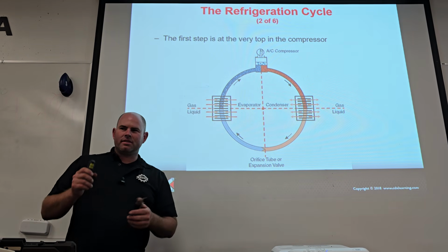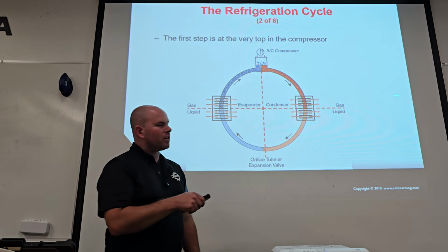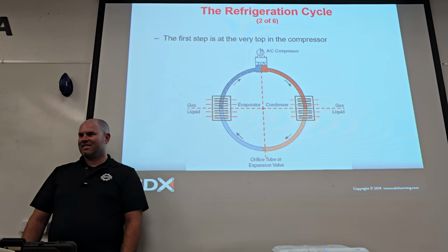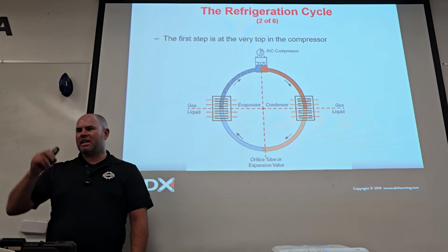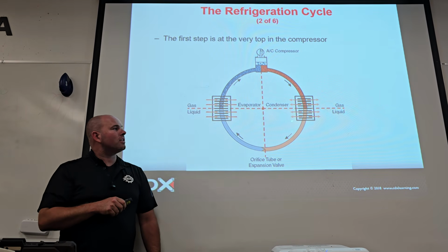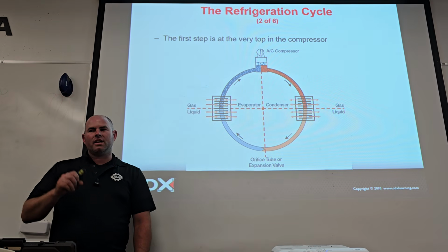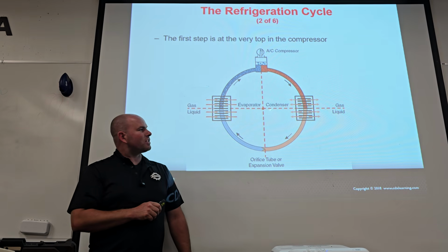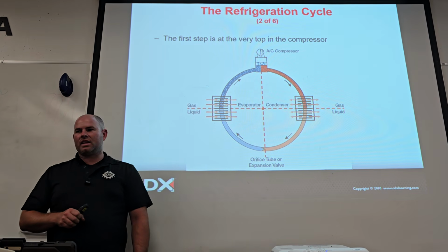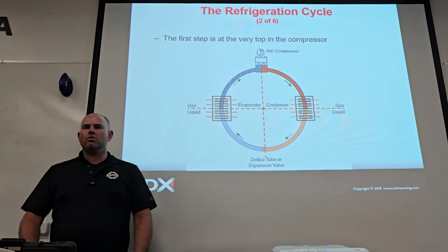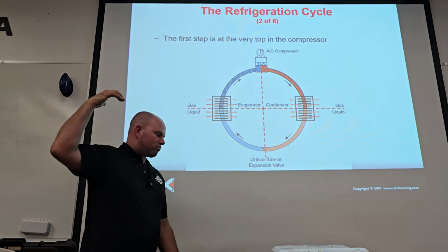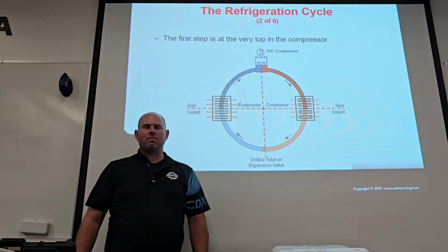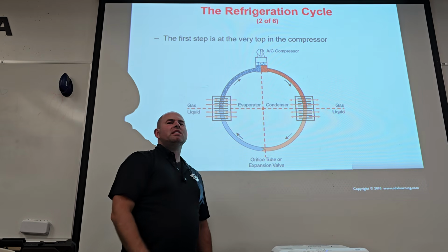However, this is what's crazy. It just dumped off a ton of BTUs. Did you know that? How did you know that, though? It might have changed a little bit of temperature, but not really, no. Because the transfer of BTUs right here is not in the sensible form. It's latent. Latent, exactly. So it came gas to liquid. Remember that? Boom, it just dumps it. So you knew it was carrying all those BTUs. And it's like, oh, gas to liquid. Boom, I dropped the BTUs. I dropped all those BTUs right there.